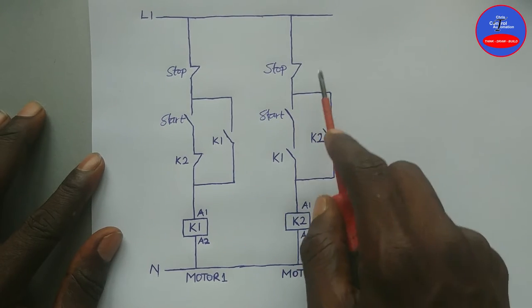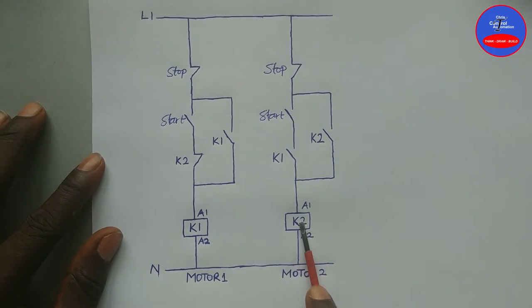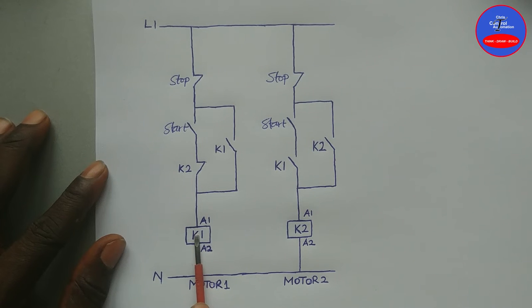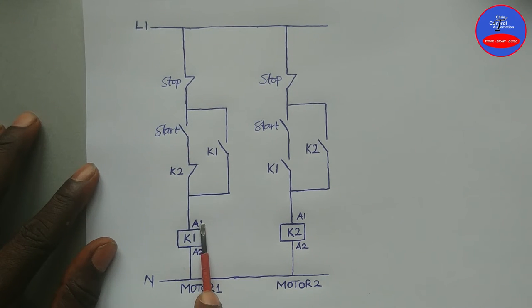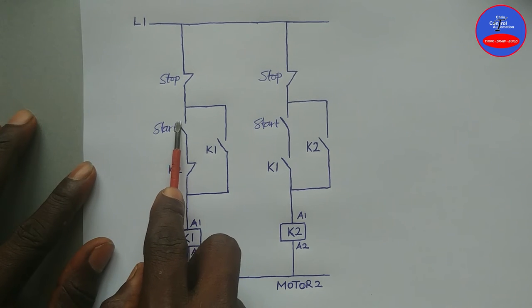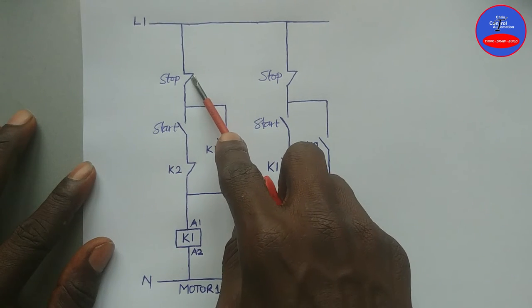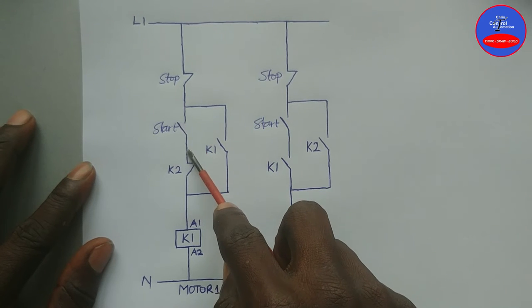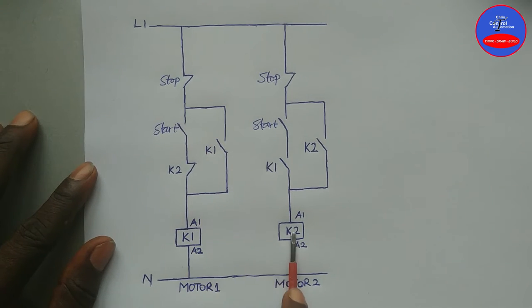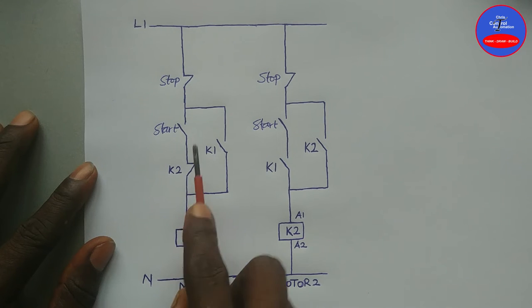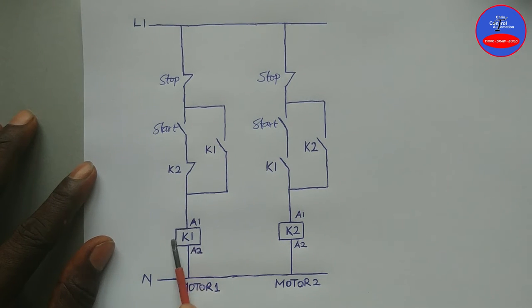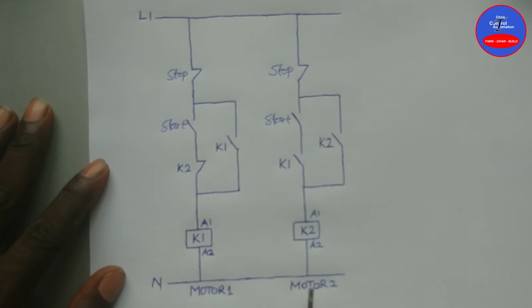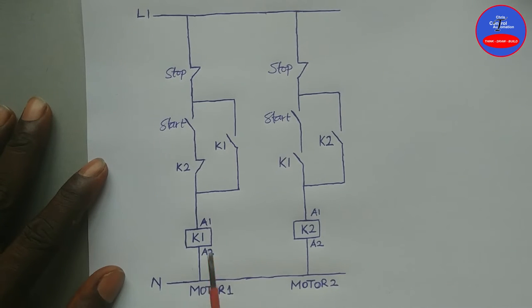In this case we can stop and start K2 at any time. But let's see K1 or Contactor 1: when we press on the stop button, Contactor 1 will de-energize. When we press on the start button again, current flows through this close contact, through this close contact, but when it gets here, because K2 is still energized this contact is open. Therefore there is no way current can flow through to re-energize K1.